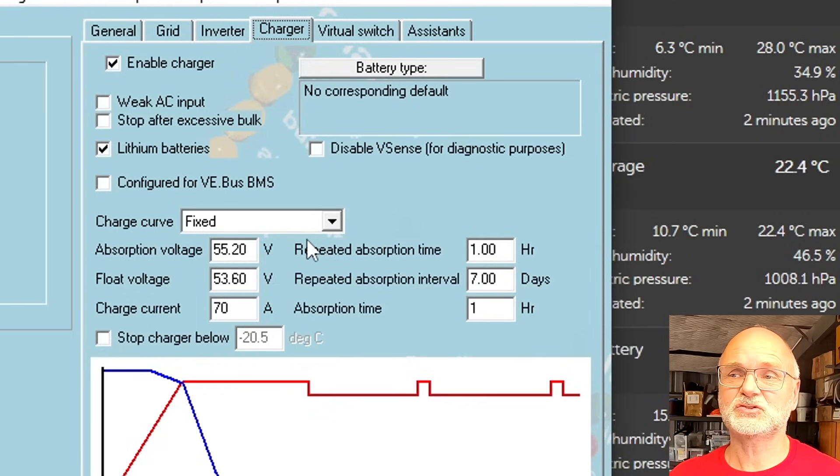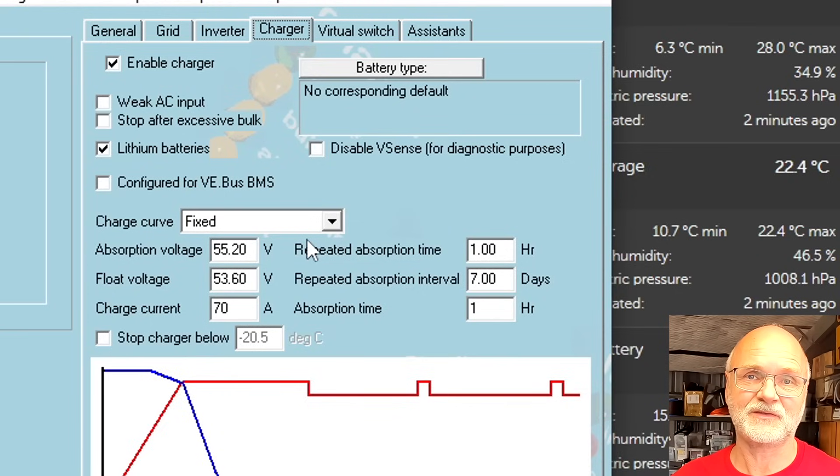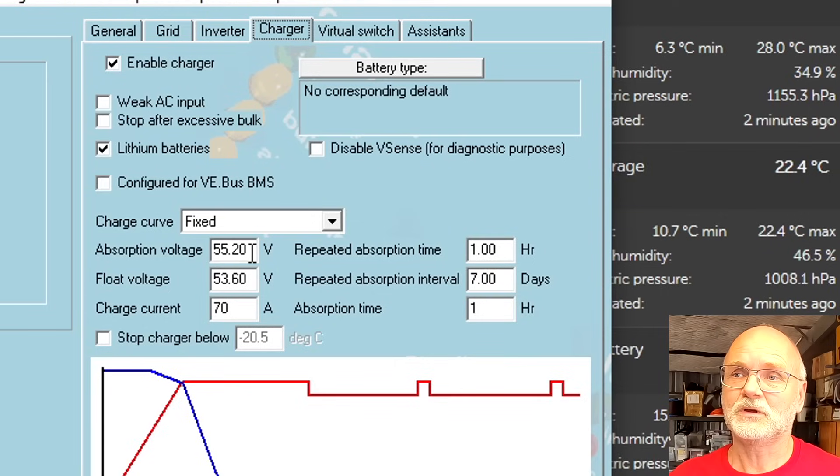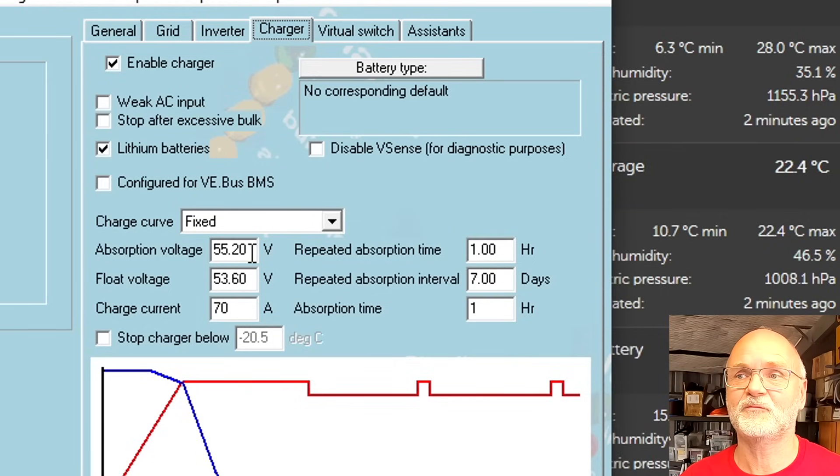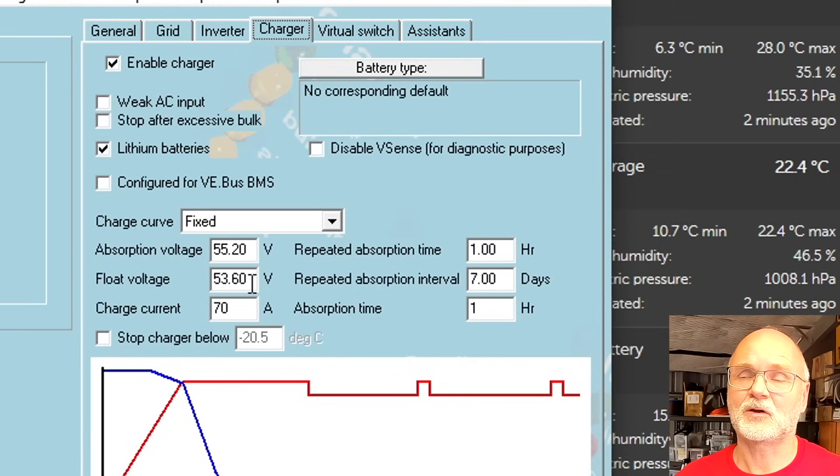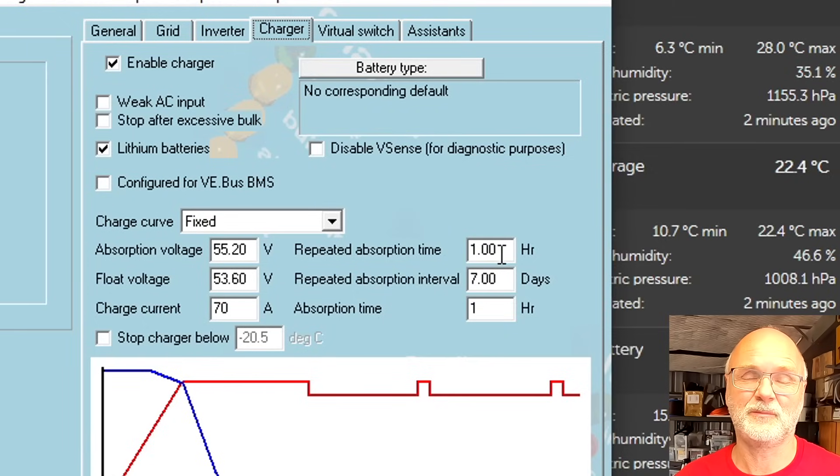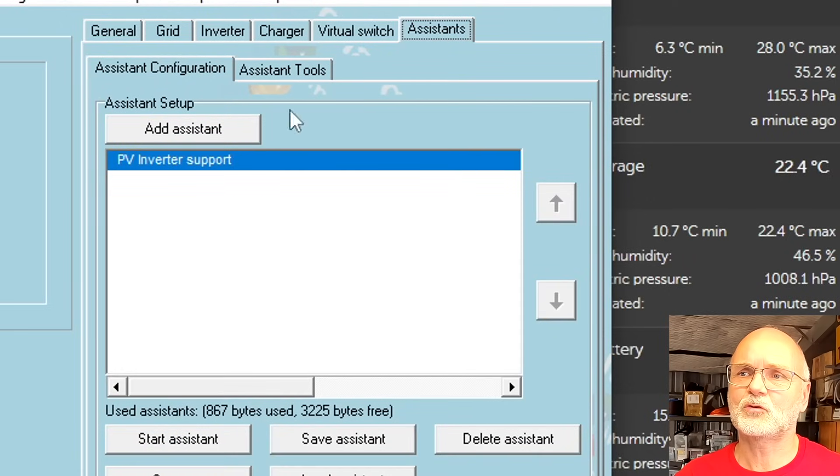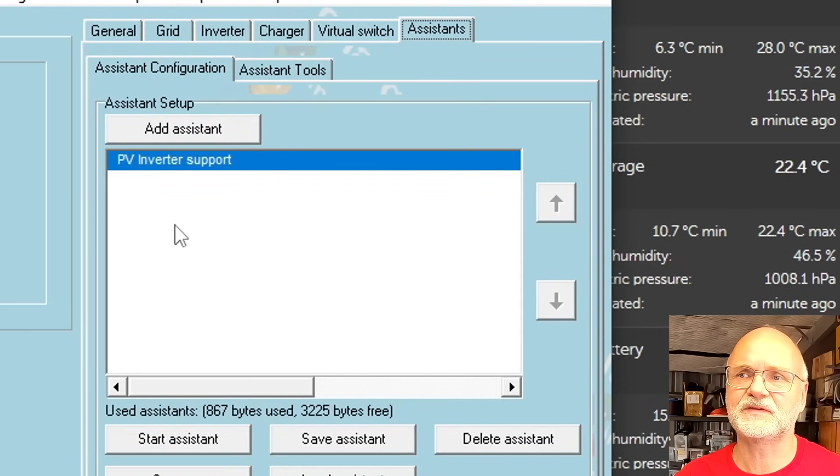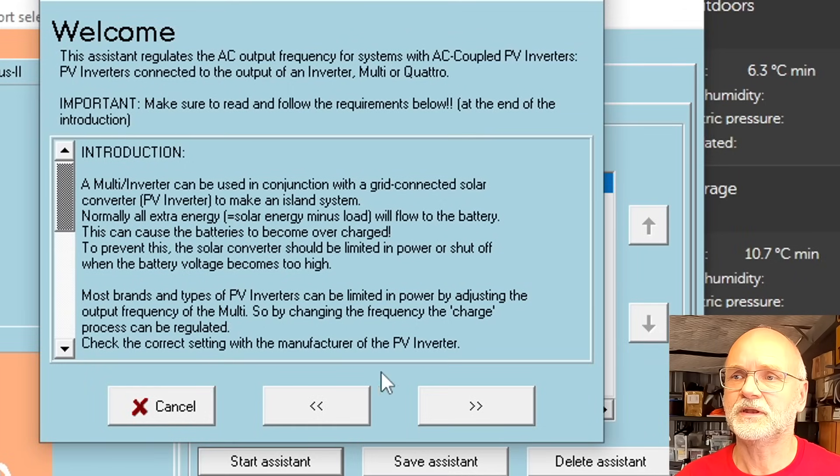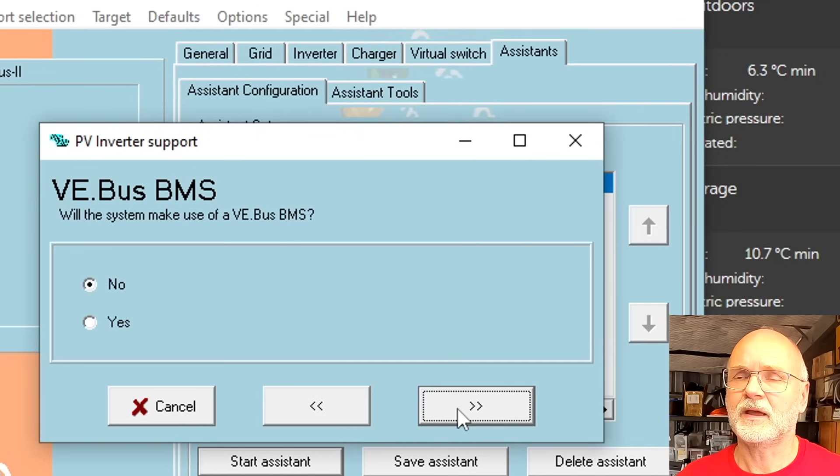I have set pretty much the same settings in our multi plus as in my solar charge controllers. We are charging to an absorption voltage of 55.2 volts, stay there for one hour, then go back to float 53.6. This one hour is purely for the balancers to do their work. The second thing you need to set up is an assistant called PV inverter assistant.